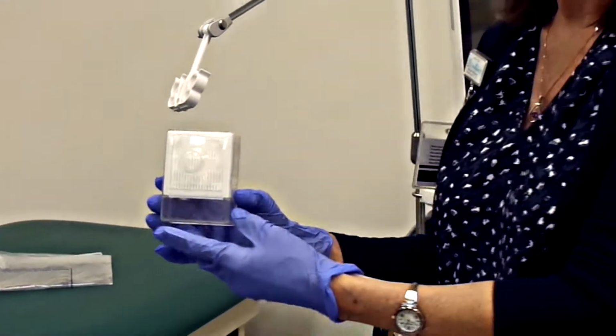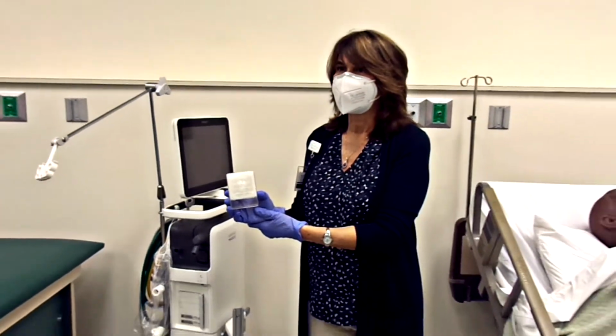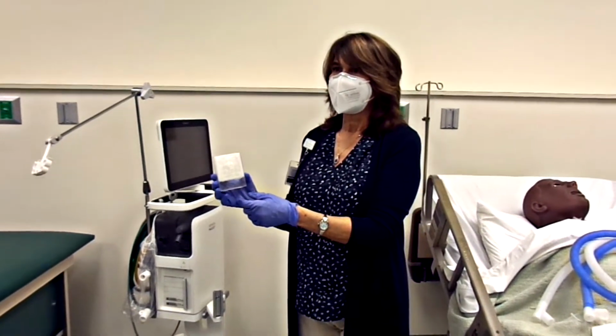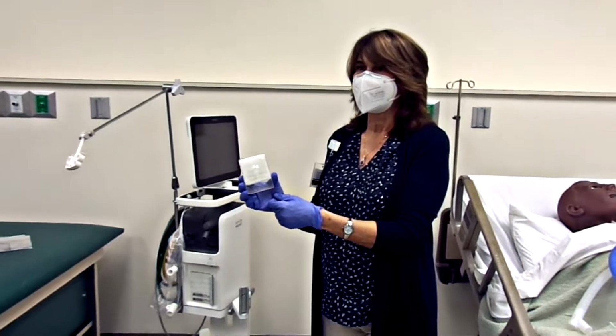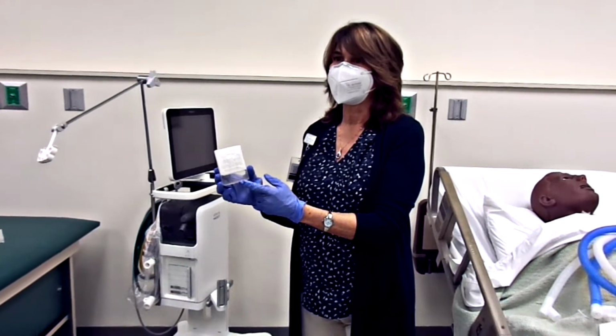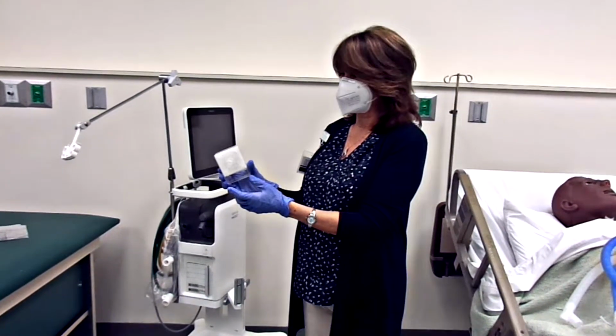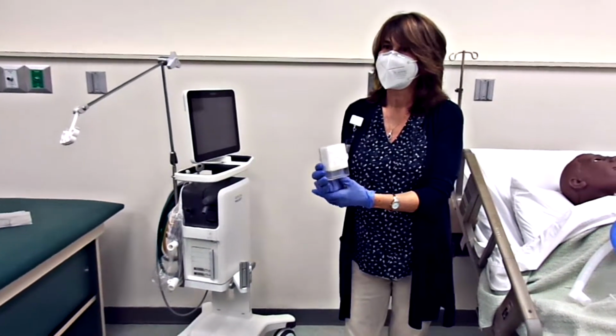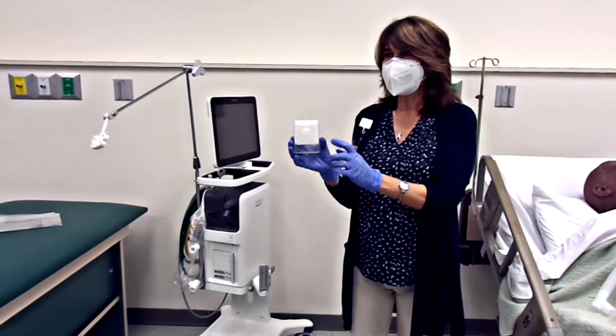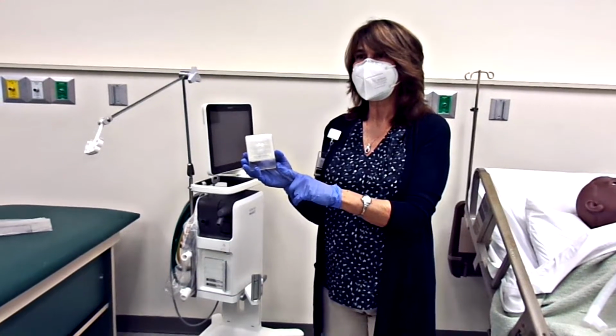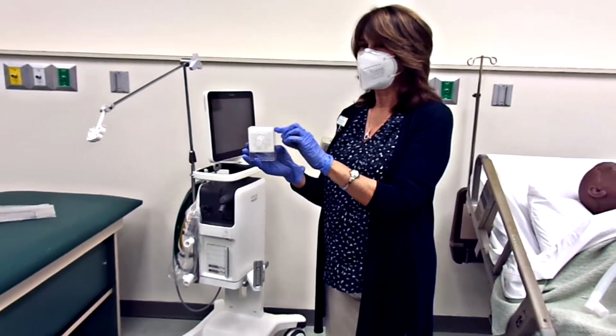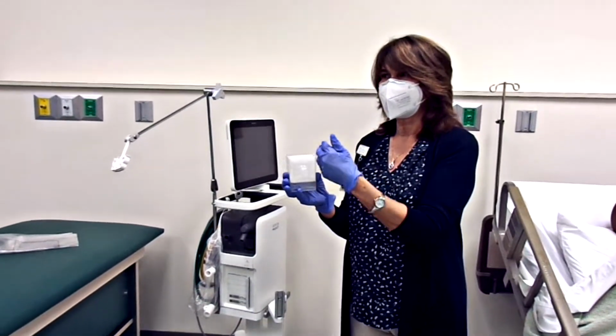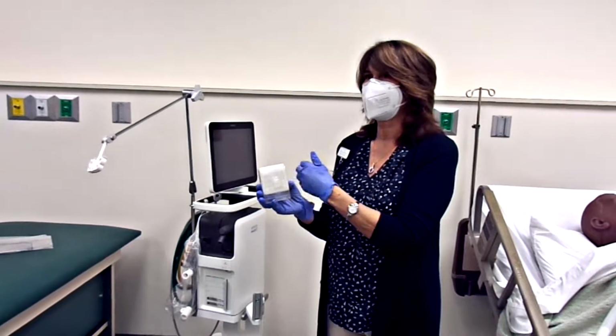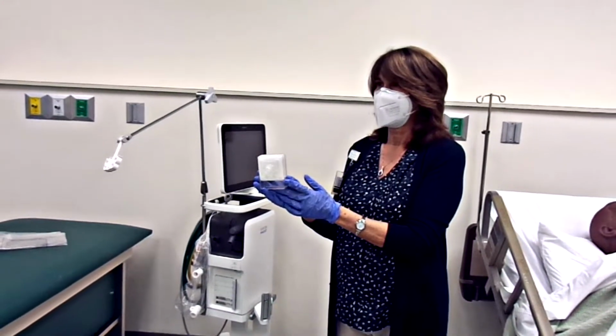Now, is there a way to release the water or the condensation or liquid that forms in there, or do we have to completely change out that filter? You throw it out completely and put another one in. For these, you throw them away every day and put a new one in, because if a lot of moisture builds up in here, it restricts the flow of air leaving the ventilator and leaving the circuit. Bacteria.